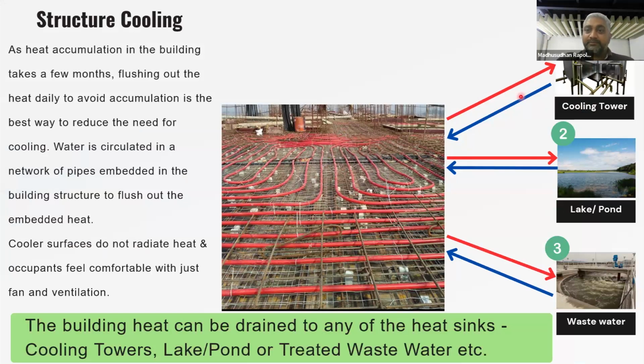You could use multiple heat sinks like a cooling tower. Could be a water body. Could be even a treated wastewater tank. Just find a heat sink where you can dump this heat so that every day that accumulation doesn't happen. If you're able to flush out, let's say from the end of February, continuing for 3-4 months, you don't allow the heat to accumulate in the building and keep chipping it off every day.